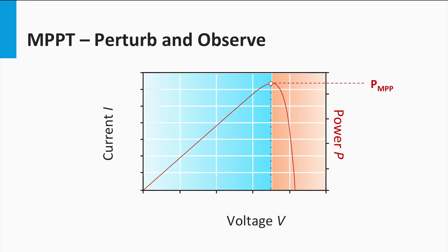We start first with the perturb and observe, or P&O, algorithm. In this algorithm, a perturbation is provided to the PV module or array voltage, which translates to an increase or decrease in power. If an increase in voltage leads to an increase in power, this means the operating point is to the left of the MPP, and hence further voltage perturbation is required towards the right to reach the MPP. Conversely, if the increase in voltage leads to a decrease in power, this means the current operating point is to the right of the MPP, and hence further perturbation is required towards the left.